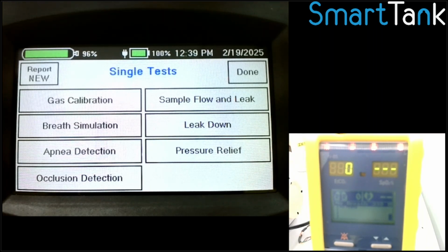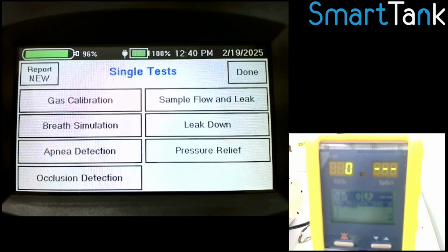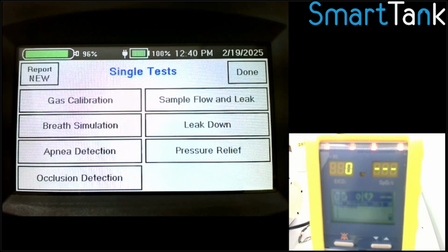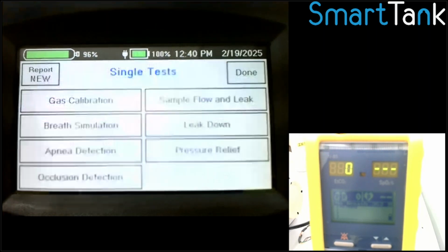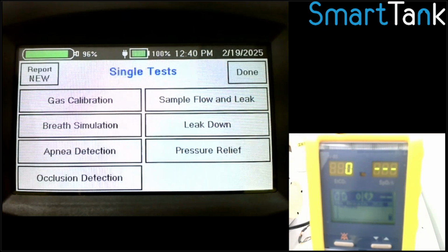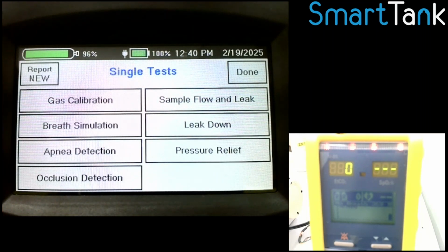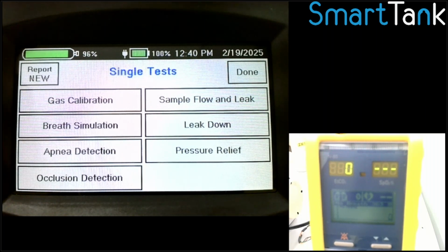It'll guide you through it. It'll do all the measurements, all the timing. It'll check for stability. And so it really just facilitates that whole process. Because we did the leak down test and have that ability, which is heavily involved in non-invasive blood pressure cuffs, we added this pressure relief test. So with the SmartTank, you can actually do all your non-invasive blood pressure cuff testing and device testing. It has all the modes you need for that.